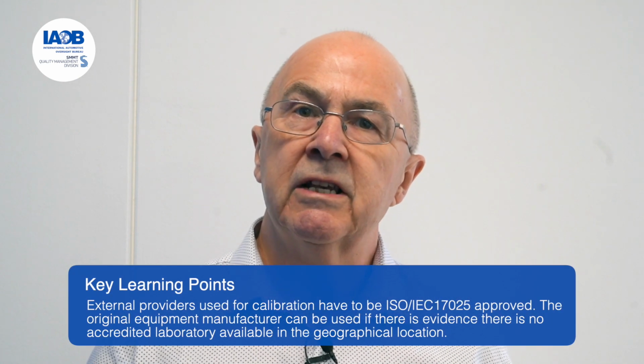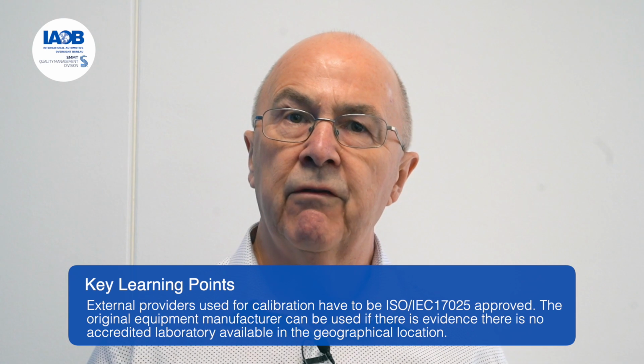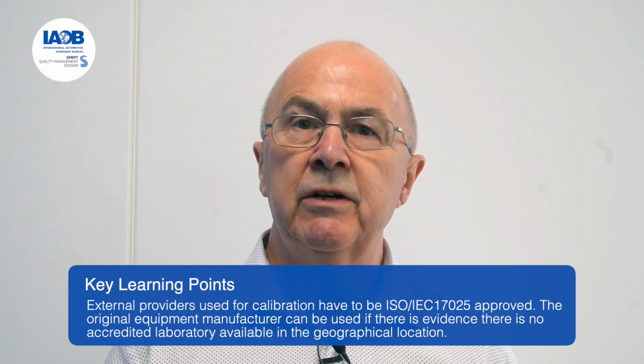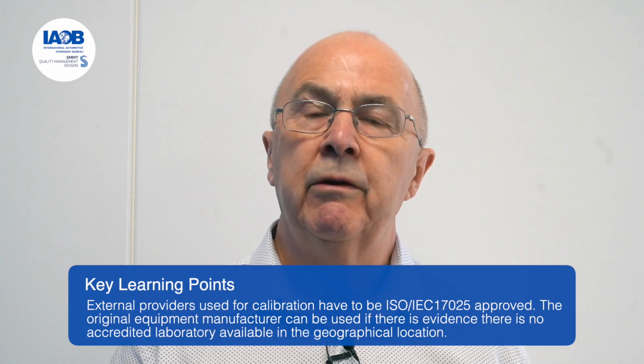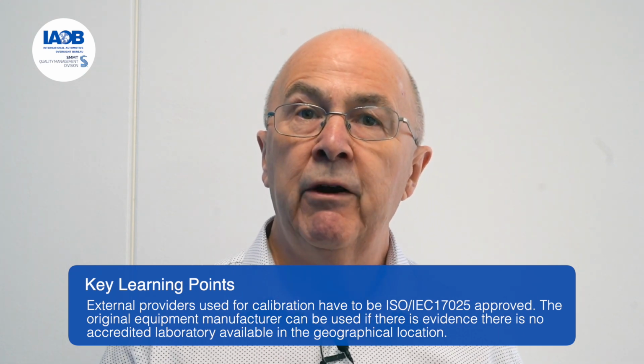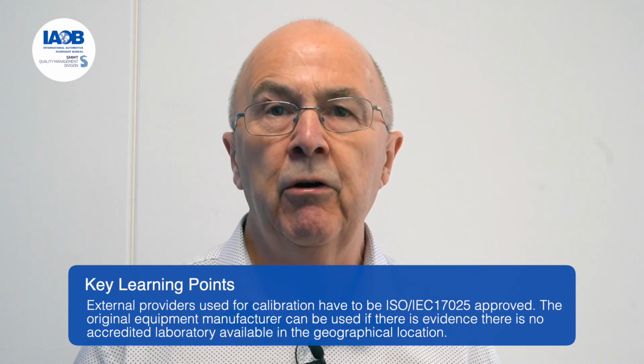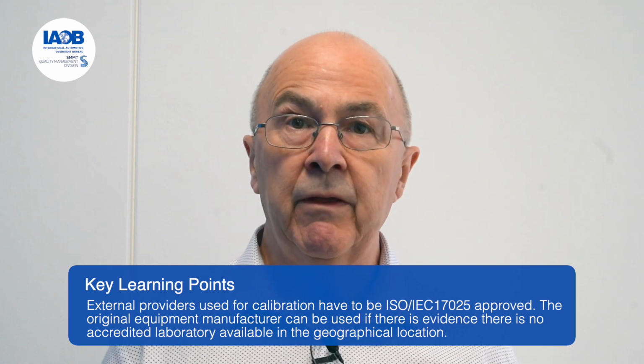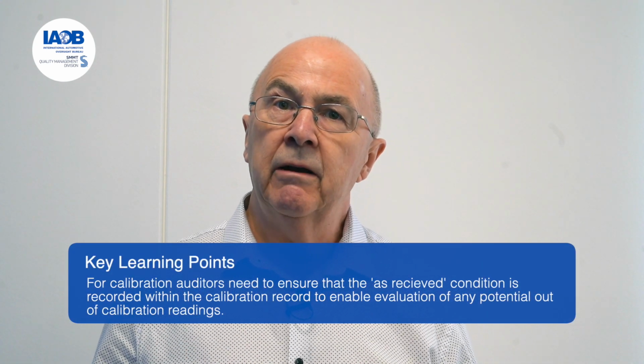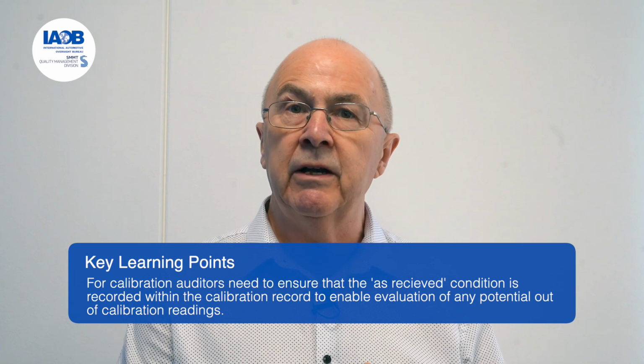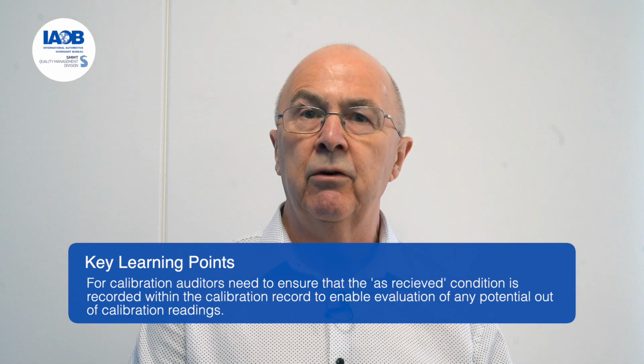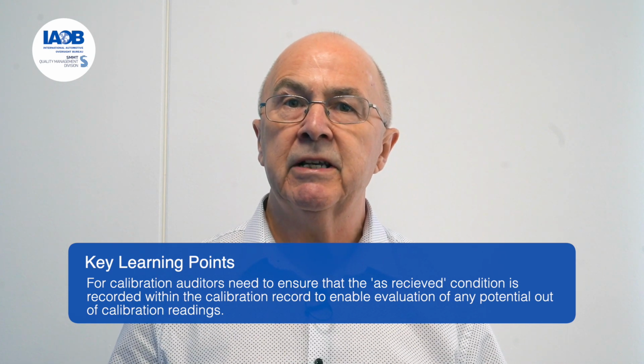So let's summarise the key learning points. Firstly, any external providers used for calibration either have to be 17025 approved, or the original equipment manufacturer can be used if there is evidence there is no accredited laboratory available, or certainly available within the geographic area of the organisation. Secondly, for calibration, we need to ensure that the as received condition is recorded within the calibration record to enable evaluation of any potential out of calibration readings. In this case, that was not being done by the external provider.